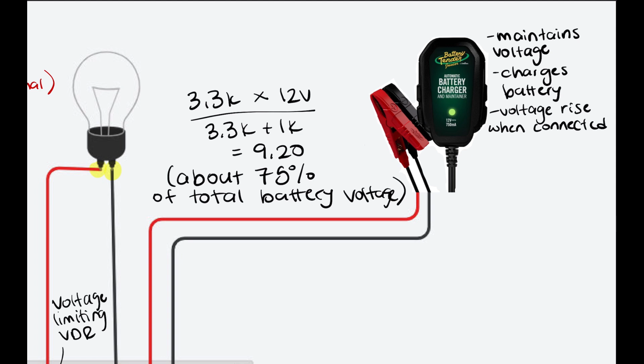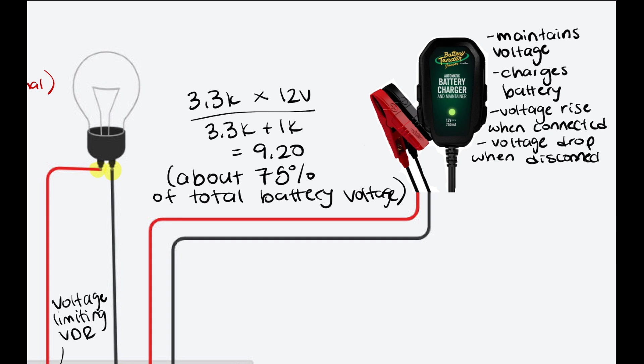The voltage rise indicates that the grid has been connected and the battery is charging again, telling us that power has been restored in the case of an outage. The voltage drop tells us that an outage has occurred, as the battery charger has been disconnected from power and can no longer charge the battery.